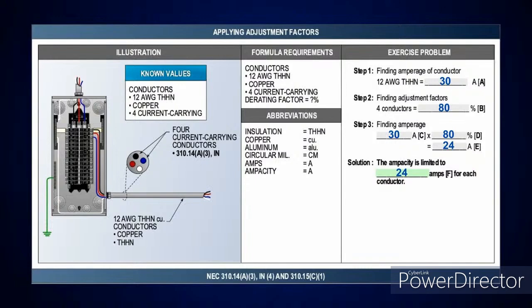We did this last week, and I said when you go over and look at Table 310.16, look at the top of it. It'll tell you that table is good for 3 current carrying conductors or less, and it's good for temperatures up to 86 degrees Fahrenheit. Once you're over that, then you've got to start looking at Table 310.15(B)(1) and Table 310.15(C)(1). So in this case, I brought this up last week. When am I going to be able to use the 90 degree C column? That's in Table 310.16. And I stated if you go over and look at 110.14(C), you pick up the last sentence in that paragraph there. It's going to talk about adjustment or correction factors. If you're applying those, you're permitted to use the highest rated terminal rating, okay? Right. Or the highest rated insulation rating, which would be 90 degrees C for the terminal.